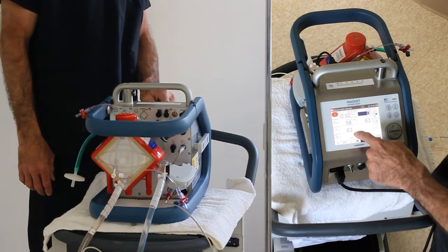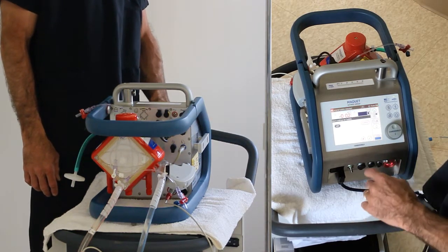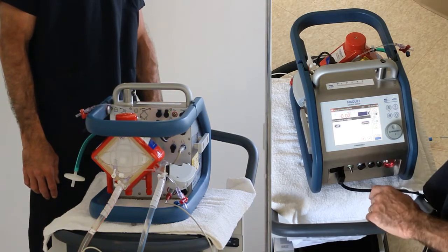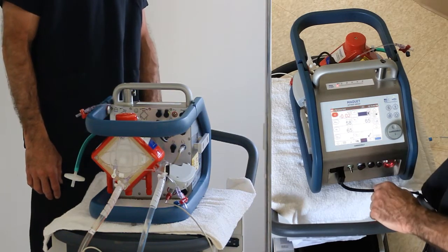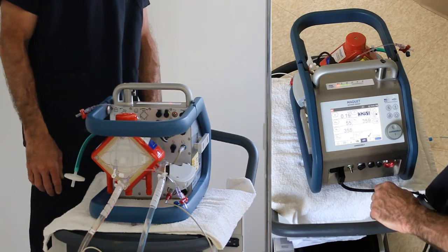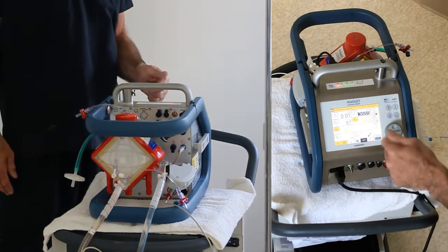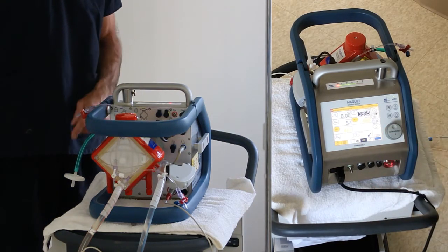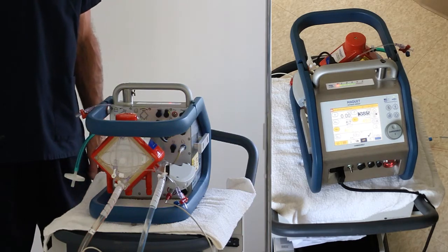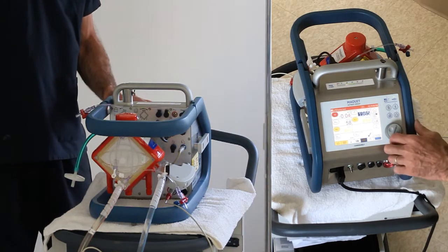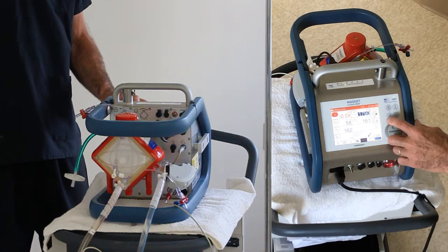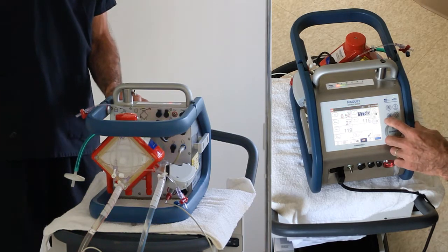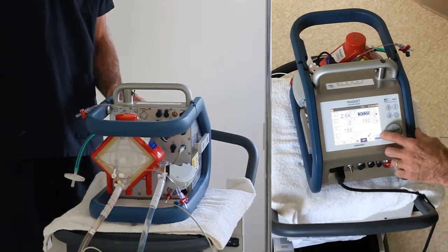We can enter the arterial bubble setting, reset that, and then enter the information. Now it's ready to go. It's going back to 3,685 RPMs, but it's zero flow because I have a clamp on over here. So let's turn this down to about 1,000 for a moment, so I'm not pushing too hard. Take the clamp off and come back up.